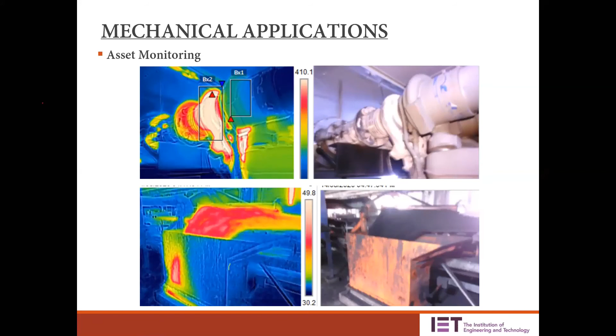Likewise, we can carry out monitoring of many other critical assets. There are V-belt systems and drivetrains—if the V-belts are over-tensioned or under-tensioned, you can tell through this technique. For valves, if they are leaking, blocked, or not operating properly, you can identify it through this technology. Steam traps, air leaks, heat exchangers, and tank level monitoring are also common applications, especially for tanks with underlying sludge layers, which you can easily detect with these devices.